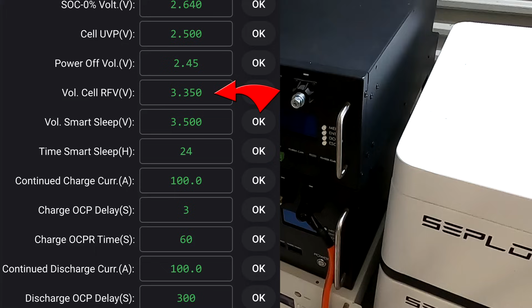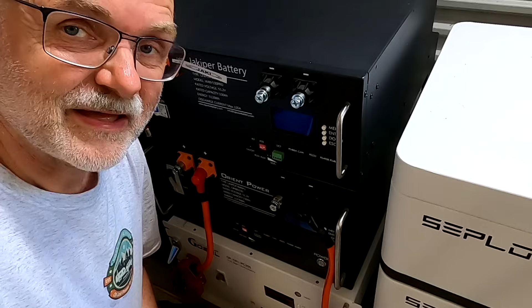And then the voltage would go back to the requested float voltage of 3.35 times 16, and we would stay there for 8 hours. This is mainly to prevent another bulk or absorption charge. So it keeps the battery on float voltage for the rest of the day, and then in the middle of the night it changes back to bulk, so it's ready for the next morning when the sun comes up again.